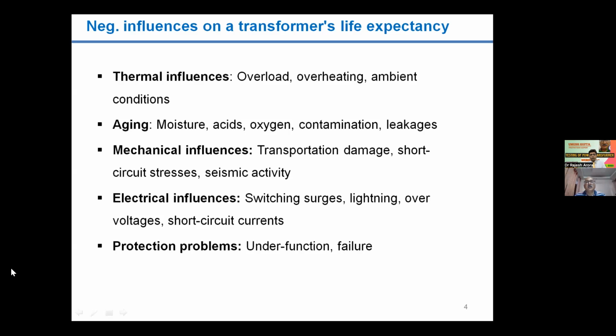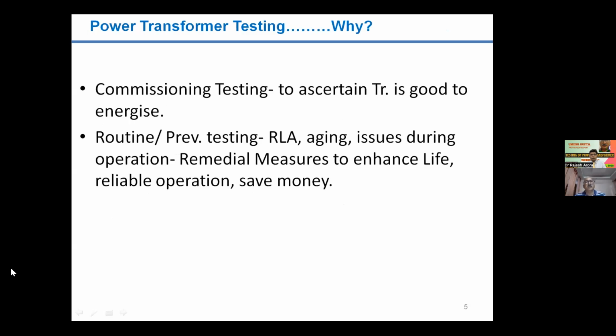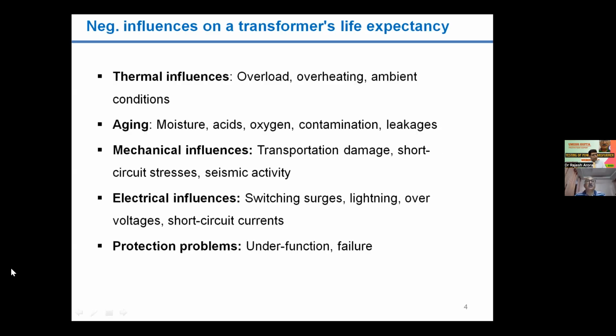Then there are chances, a few times it also happens that the protection which is installed maybe on our outgoing feeders or the transformer LV side may fail to operate, and the fault is cleared after some time. It may be delayed due to operation of the next line of defense protection. So because of these reasons, problems may also be there with the transformer or its components inside, winding, insulation, etc. Next.